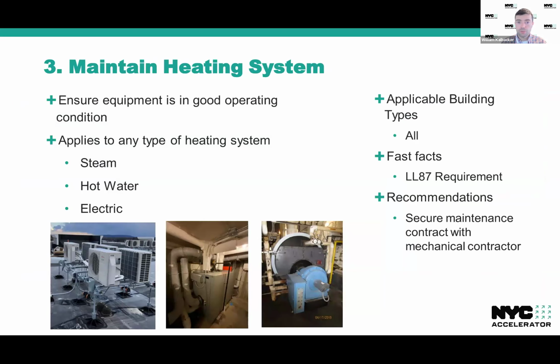Measure number 3 is to maintain the heating system. This one is basically just to ensure that all of the equipment is in good operating condition. It's going to apply to steam, hot water, and electric systems. This is sort of just general best practice stuff. Keep things clean, keep things operating, keep things smooth and greased. It's going to apply to all building types. This is also very much a Local Law 87 requirement. A lot of buildings have a maintenance contract with a contractor that will come in on a regular basis and perform this service. So it very well might be something that hopefully most buildings are doing already.